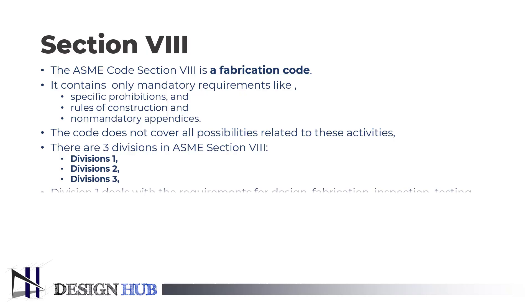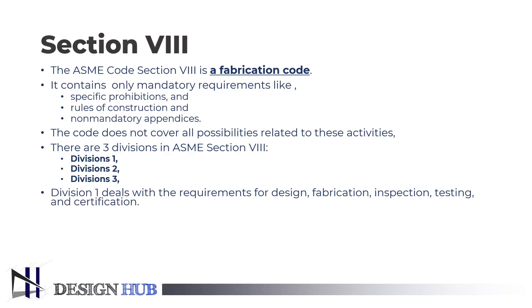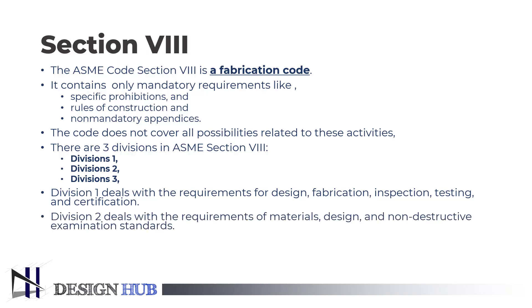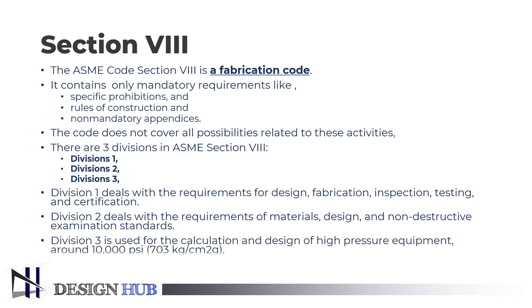Division 1 deals with the requirements for design, fabrication, inspection, testing, and certification. Division 2 deals with the requirements of materials, design, and non-destructive examination standards. Division 3 deals with the design and calculation of pressure vessels significantly working at a very high pressure range, above 10,000 pounds per square inch. Moreover, let us see what Division 1 is all about.